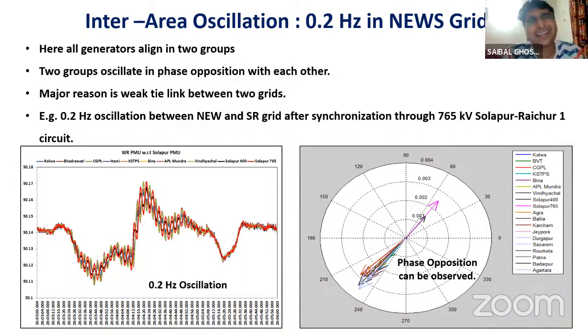2013, I think in the month of December, it was connected with some 765 kV line in Raichur Solapur. So that means it is very poorly connected. These two systems are connected by only two very weak links, and that's why these two systems used to oscillate against each other. And here is the signature of the oscillation that is being captured in the PMU.